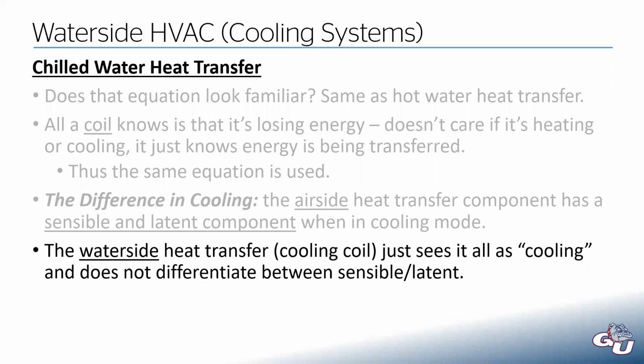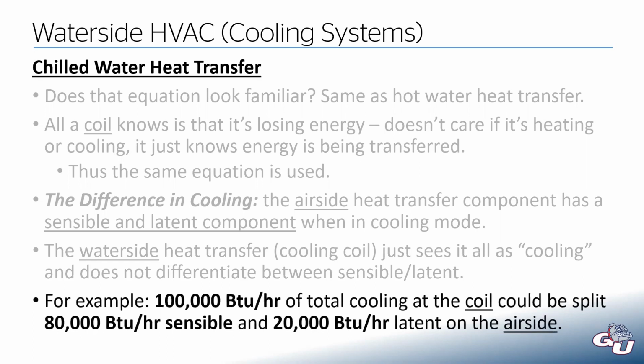It's just all cooling. So for example, you could have 100,000 BTUs per hour of total cooling at the coil side. So that's how much energy the fluid is extracting out of the airstream to cool it down. And on the air side, that could be split between 80,000 on the sensible and 20,000 on the latent. But as far as the coil is concerned, it's all cooling. It doesn't know what's sensible and what's latent, because on the water side, there is no latent load. We're not changing state, which is what's going on with the latent load. We're taking water vapor and condensing it.